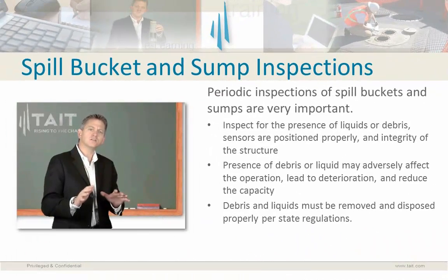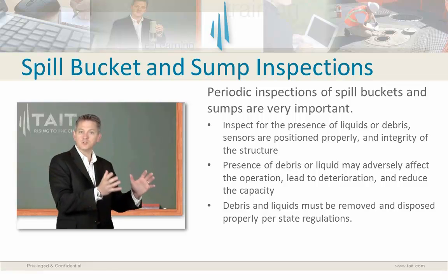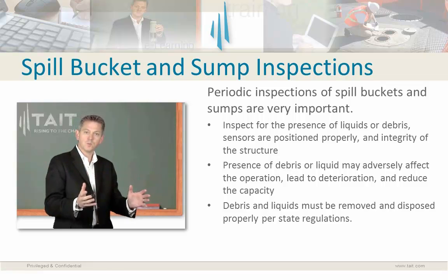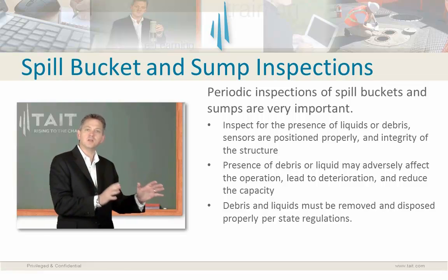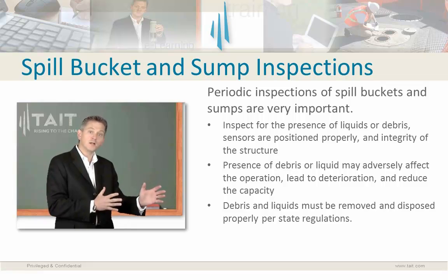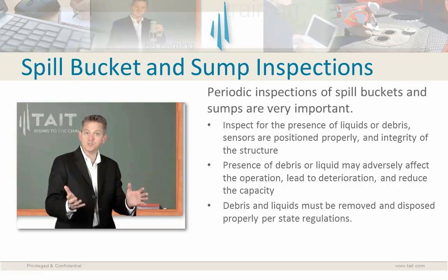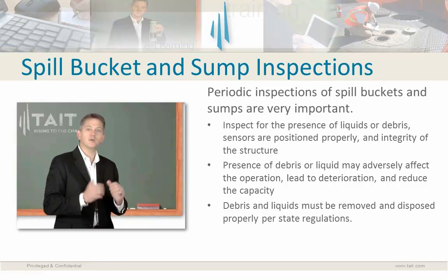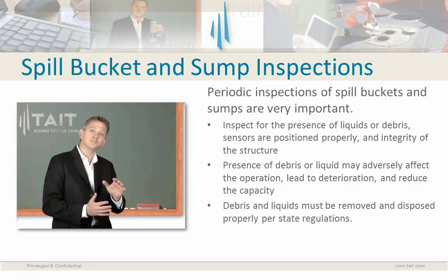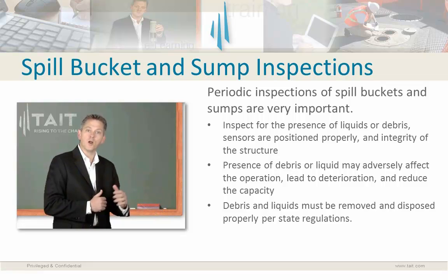Now, we've discussed the importance and the function of spill containment structures or spill buckets. Let's talk a little bit about the inspection and the maintenance of both spill buckets and sumps. Now, it's important that spill buckets or spill containment structures and our sumps are free of liquid and debris, and that if sensors are installed in those sumps, that they're installed in the proper location.